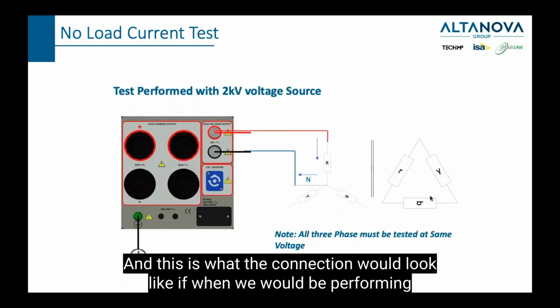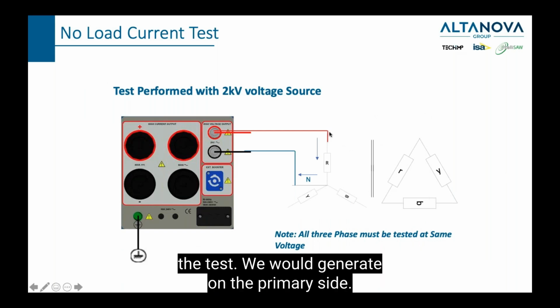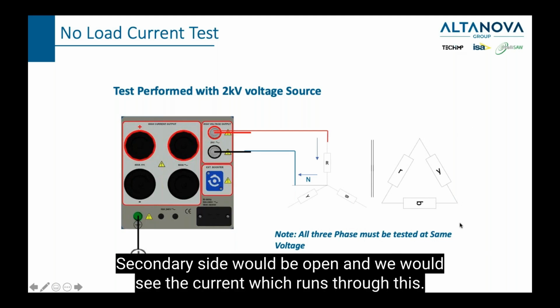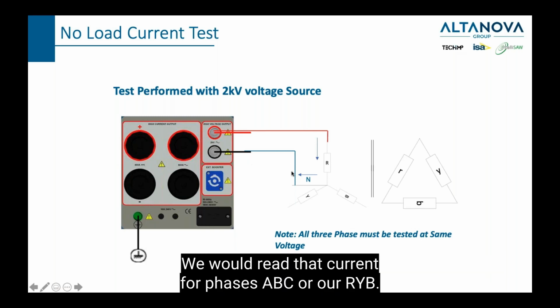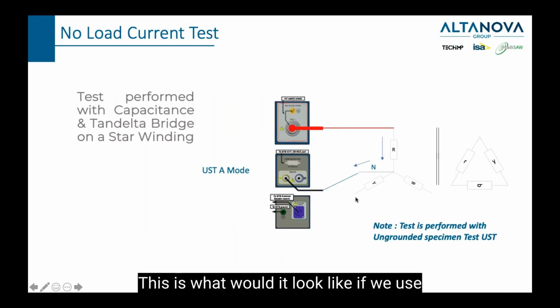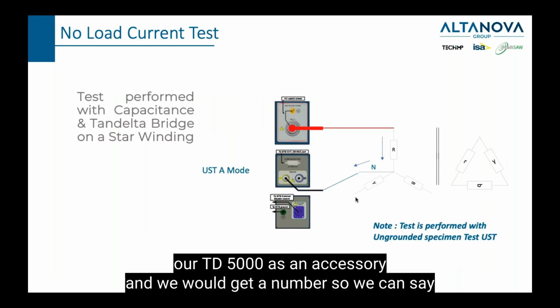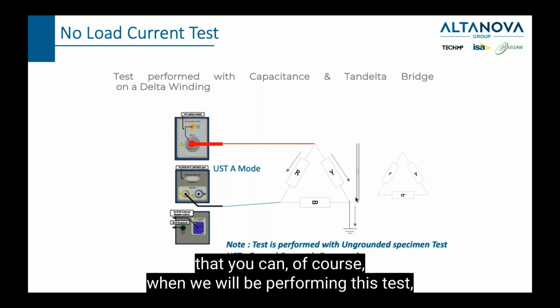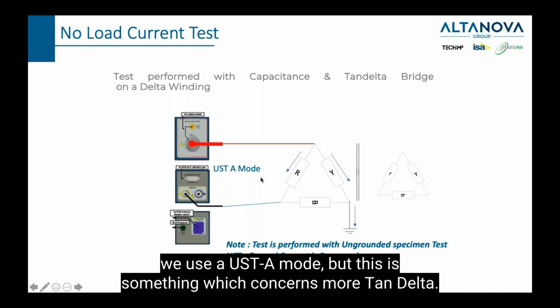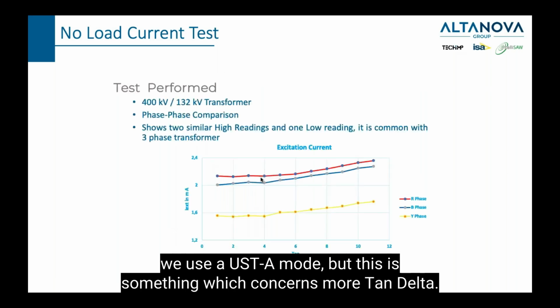And this is what the connection would look like when we would be performing the test. We would generate on the primary side, the secondary side would be open, and we would see the current which runs through this. We would read that current for phases ABC or RYB. This is what it would look like if we used our TD5000 as an accessory, and we would get a number. Of course, when we perform this test we use a UST-A mode, but this is something which concerns tan delta more.